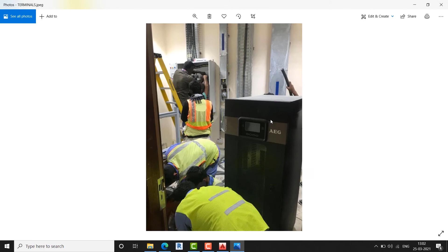From the AC supply, the batteries are charging, but the outgoing, you can see here dotted, is not going because the incoming is already present. So the outgoing is not active, the batteries are not supplying, but the batteries are charging. From here it goes to the converter, to the inverter, to the load. These batteries are charging.